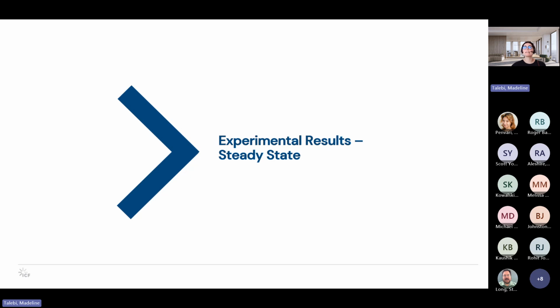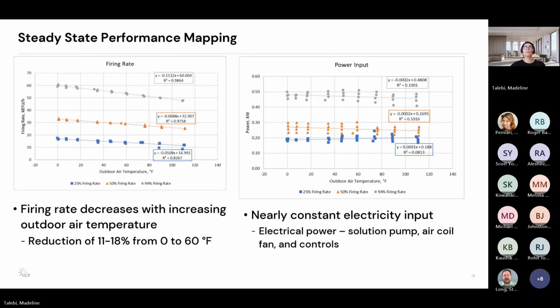So this is for the steady state testing. First and foremost, looking at the firing rate. These gray, orange, and blue curves correlate to the maximum firing at 94%, the median, we can call it 50%, and then the lowest at 25%. As you can imagine, the gray curve is always going to be at the top just because it's at its highest firing rate. You can see that the firing rate decreases with increasing outdoor air temperature, and this is a reduction of about 11 to 18% from 0 to 60 degrees Fahrenheit.